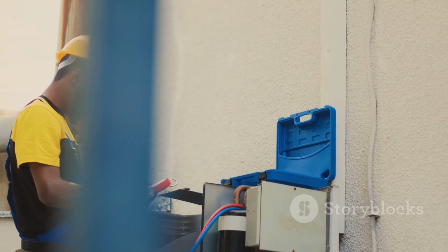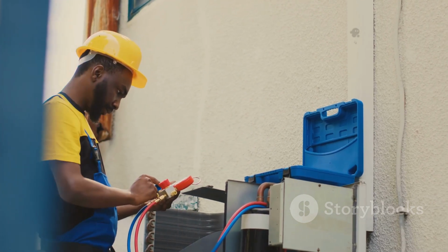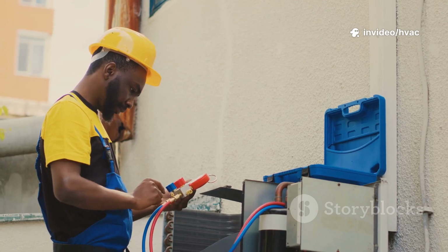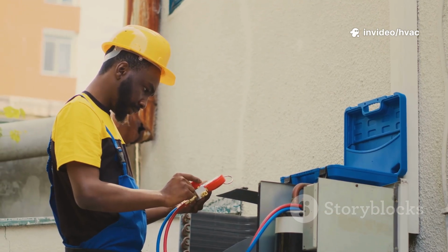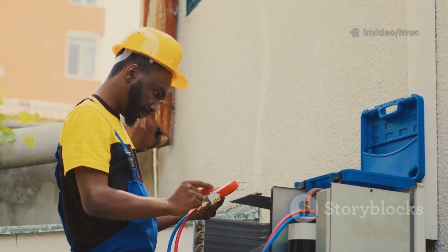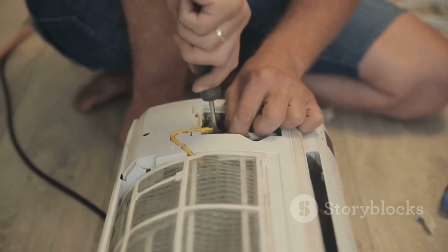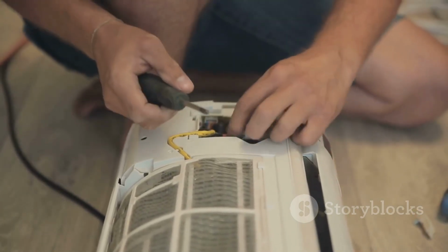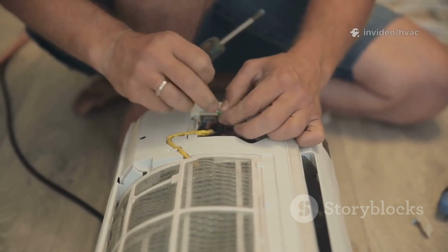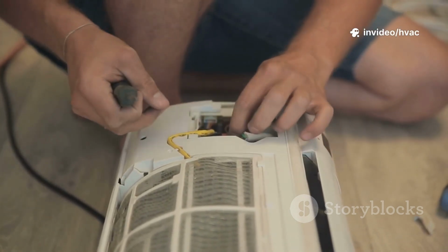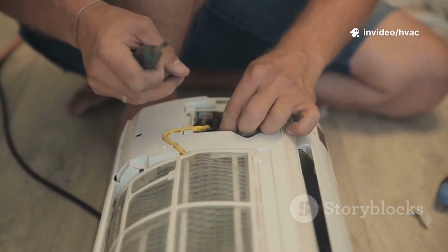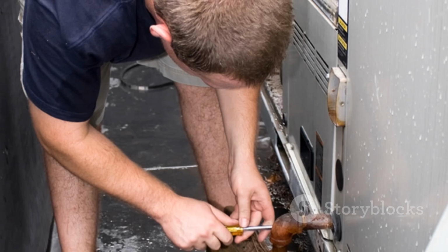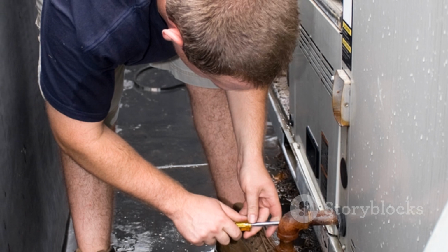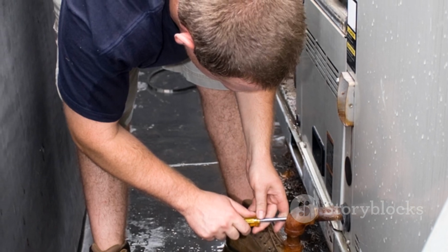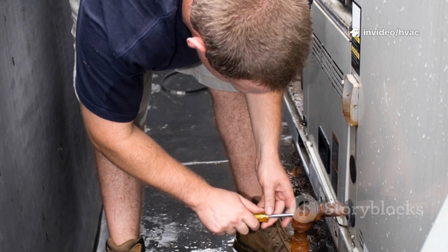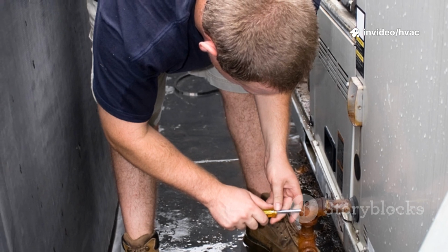Cutting corners on interlocks is never worth the risk. A single shortcut can lead to costly damage, serious injury, or worse. It's never just about getting the job done quickly, it's about getting it done safely and correctly every single time. Always understand the control sequence, respect the interlocks, and never bypass them. Take the time to study the schematics, double-check your wiring, and confirm that every safety device is in place and functioning as intended. If a safety device is faulty, replace it. Never use a jumper wire. A temporary fix can have permanent consequences. The right part, installed the right way, is the only solution that keeps everyone safe.